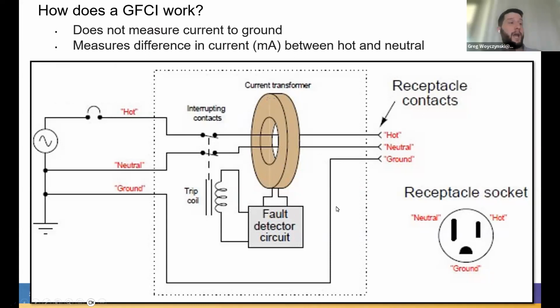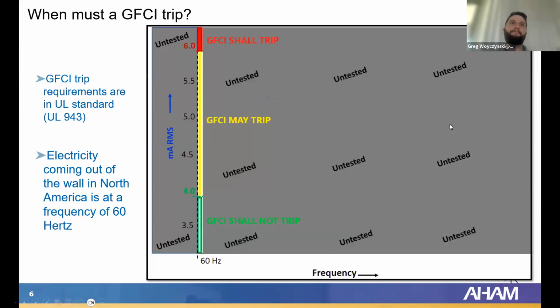And if it's being passed to ground, that means that maybe a consumer can come in contact with that current. So if that differential current is high enough, it could mean that there's something hazardous going on. There's a hazardous current to ground. So something to keep in mind, GFCIs are not measuring on the ground conductor. They're measuring a differential current.